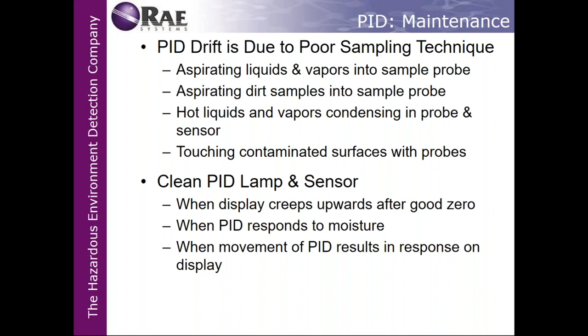When to clean a PID is usually when the display creeps upward after a good zero. So let's say, for instance, you turn on your monitor and it's reading 3.8, 4.2, 2.9, it's bouncing around. So your first instinct is you're going to want to zero it out. So you do a good fresh air zero, and then all of a sudden, 20 seconds later, it goes to 1.5, 0.8, 2.2, drifting around, it's jumping around. Chances are your probe is dirty.